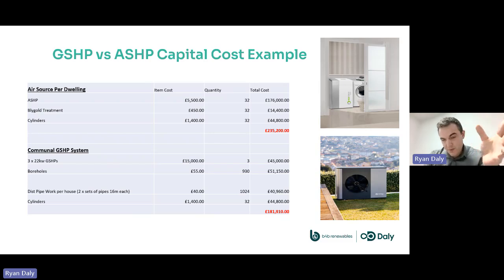Whereas if they were happy, it was a community that's going to look at potentially older people. So I put forward the notion of the communal system: three, not large, 22 kilowatt ground source heat pumps. Bearing in mind the buildings had a heat load of around 2-3 kilowatts potentially. So you put in an air source heat pump to do that heat load. It's quite a small heat load. It nearly doesn't justify putting in a heat pump, but that's the option the architect had preferred.